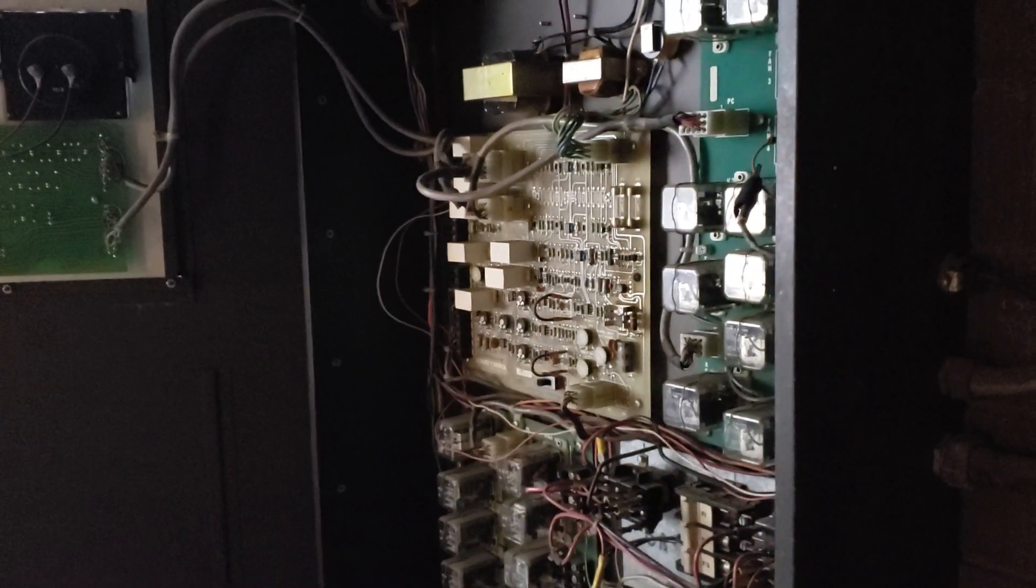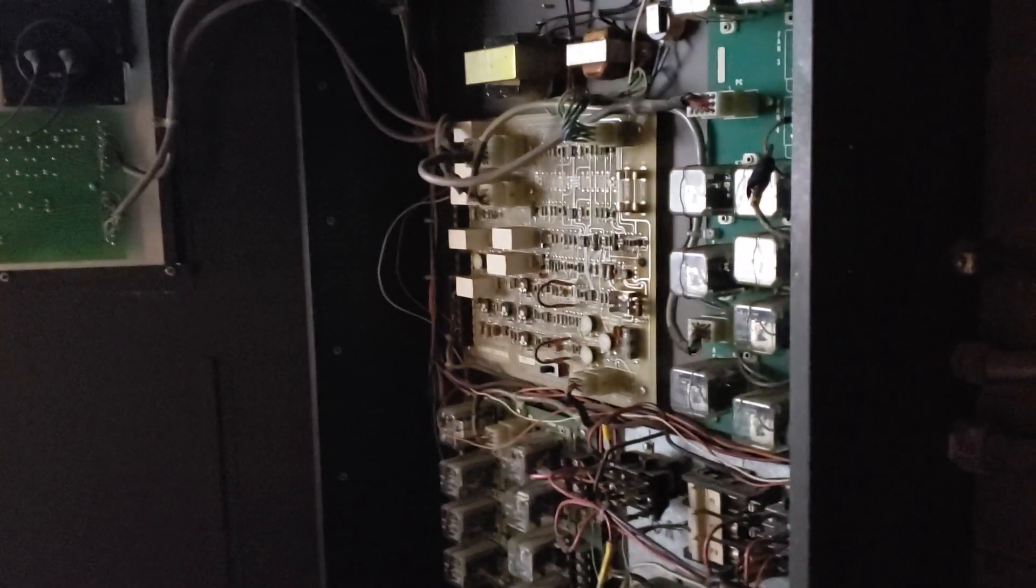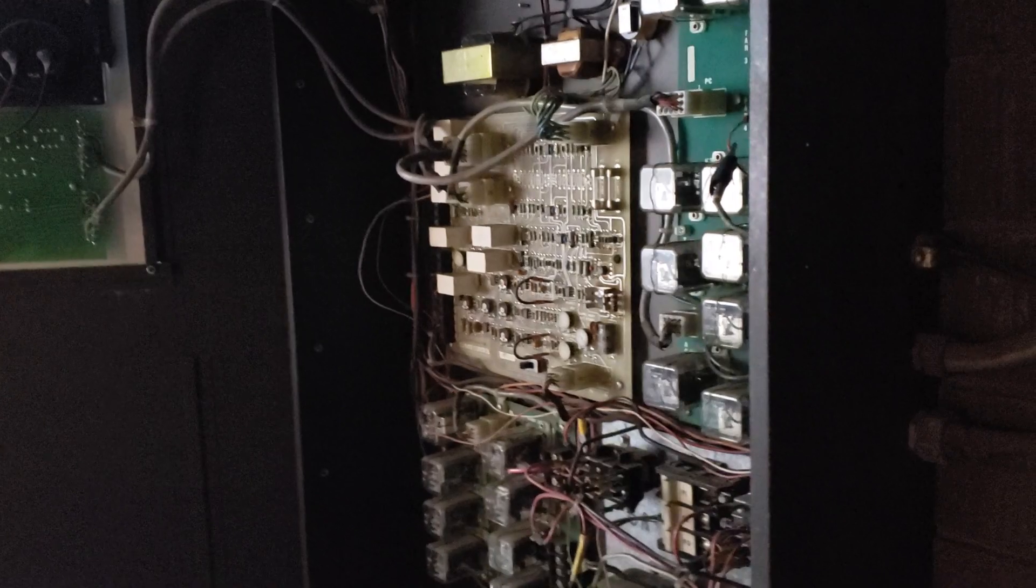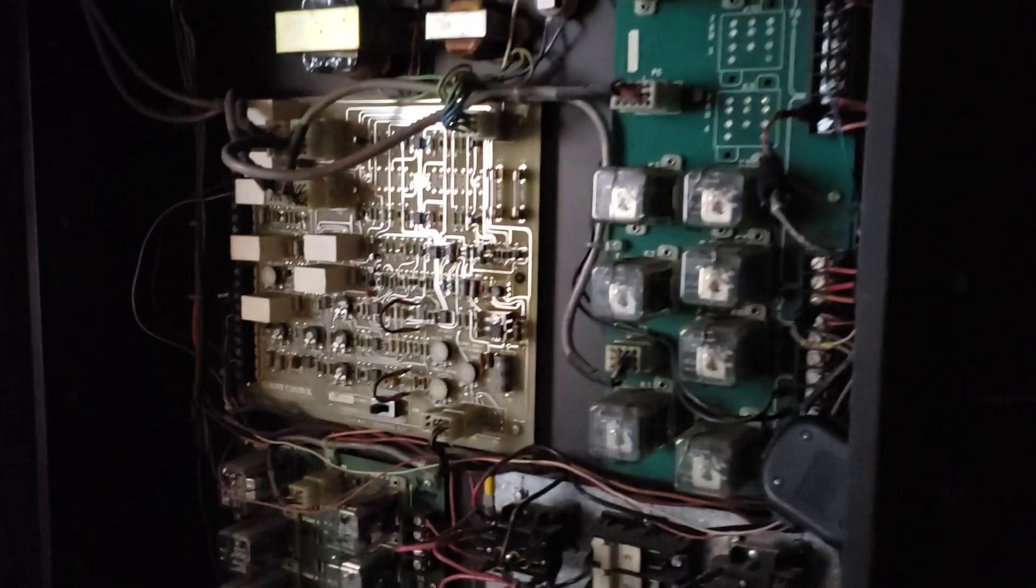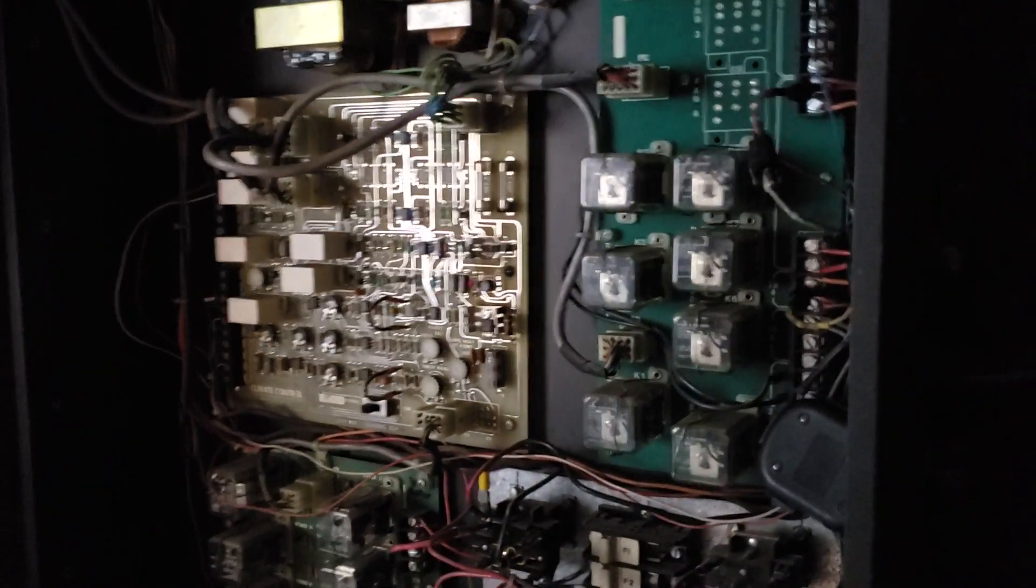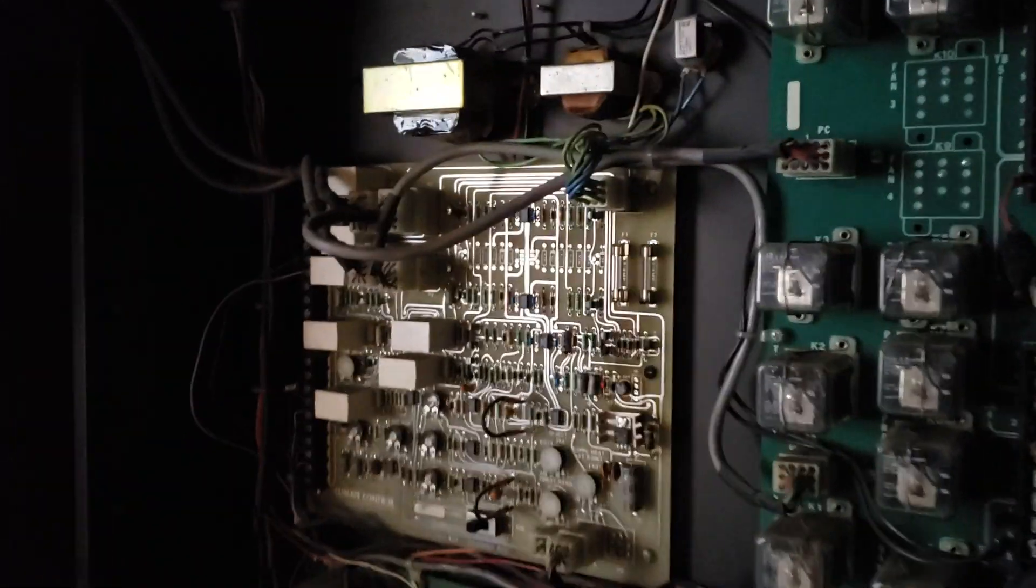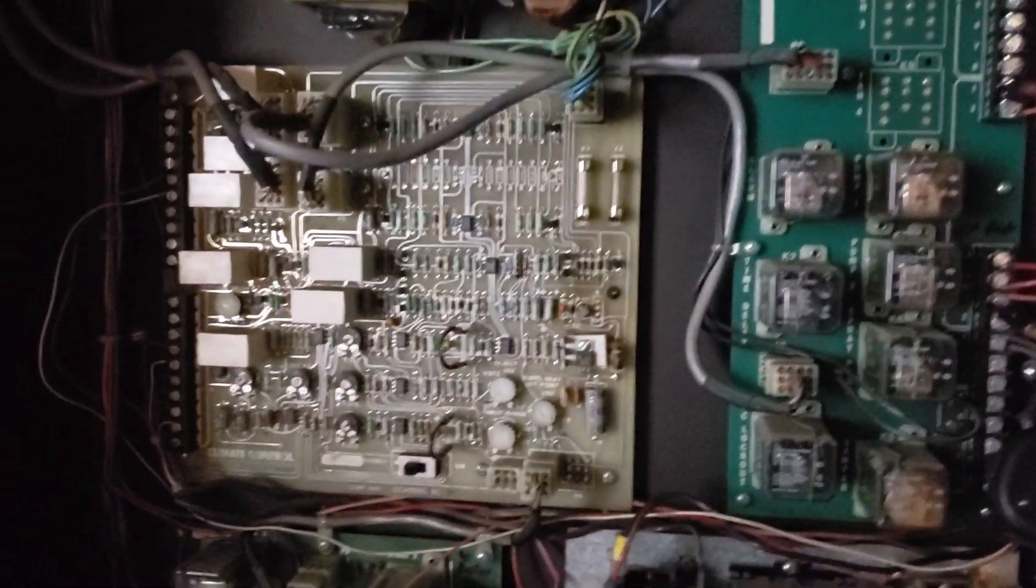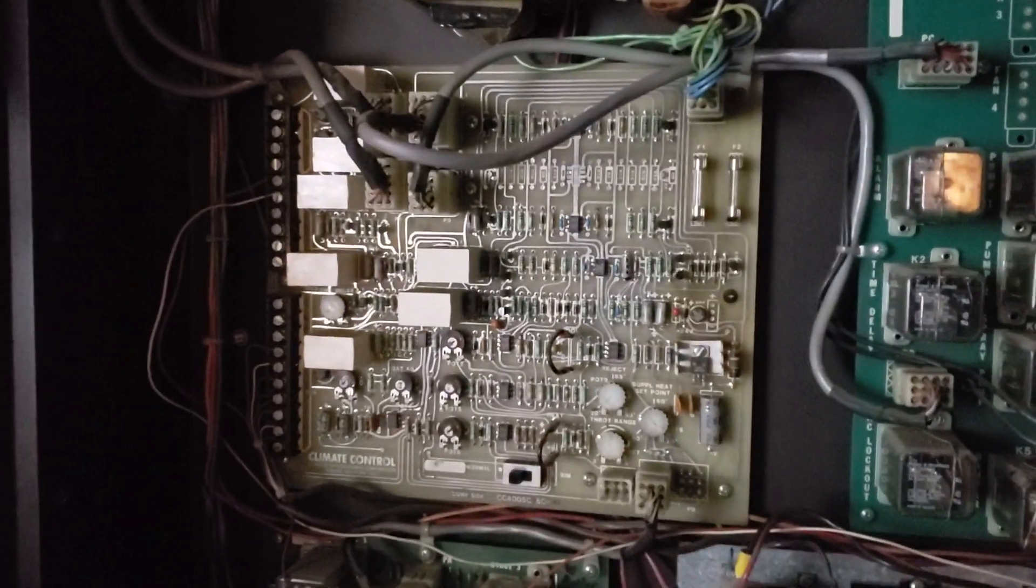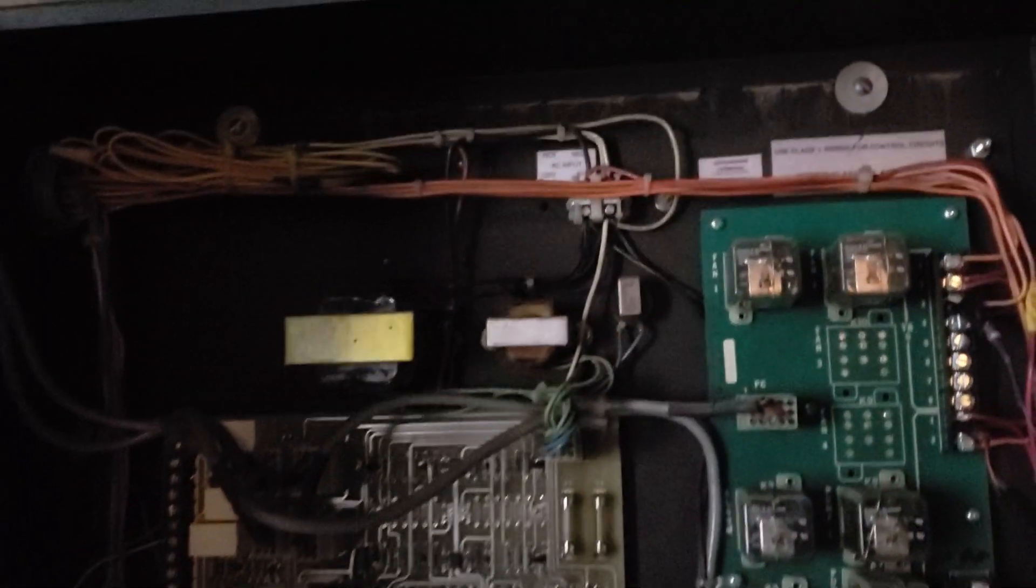I says, you have no way to come out here and just turn on a pump and a tower and get your whole building back up. Somebody like me would have to come here and figure it out and start jumping stuff just to get temporary operations. But if we were to drill some holes and put some toggle switches right there, that would work, at least for doing maintenance and for emergency. This old stuff, it's still running from probably like 1980 or something like that.